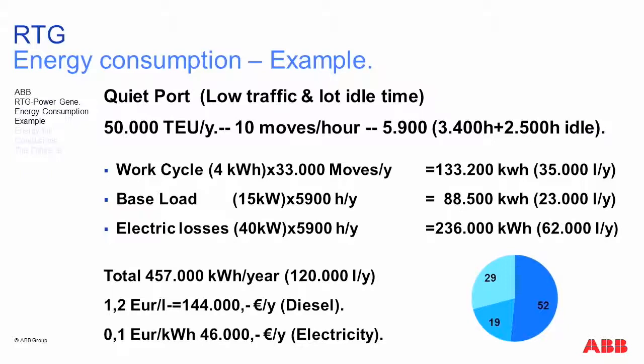For the work cycle, considering this 4 kilowatt hours, we'll have something like 33,000 moves per year, giving us 133,000 kilowatt hours consumed a year. The base load, at 15 kilowatts, gives 88,500 kilowatt hours. And the electrical losses, the bad boy, is something like 236,000 kilowatt hours.